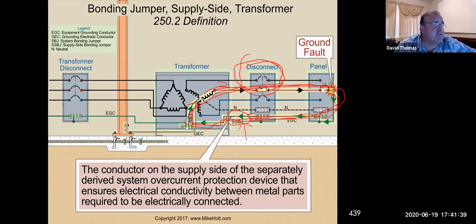So during ground faults, if we allow the ground fault to have a free flow back to the source, we will have enough current to trip the breaker. That's how our systems work: we want the breaker to trip under ground fault conditions. Other places don't ground their systems, and they don't want the breaker to trip, but it could create a dangerous situation where the equipment is like a live circuit, and if you touch another wire, you will complete the circuit, and it can become extremely dangerous with the higher voltage.